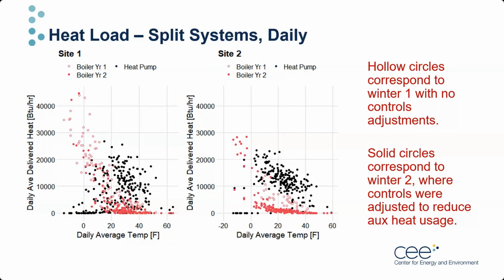Displayed here is daily data for average heat delivered in BTU per hour on the y-axis, plotted versus outside air temperature on the x-axis for sites 1 and 2. Here, the black data is output delivered from the heat pump, and the red is from the boiler. We'll see the same data wrapped up in a cleaner diagram on the next slide, but what I want to call out here is the boiler data from year 1 versus year 2.